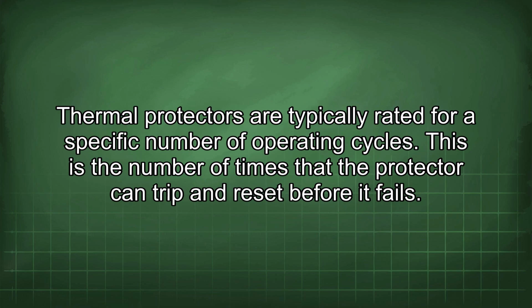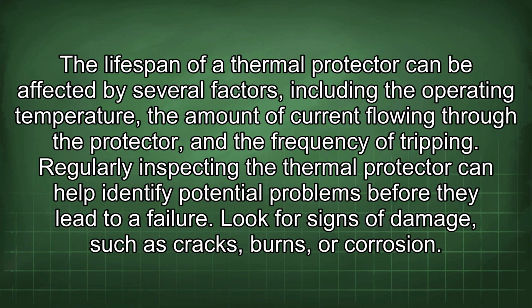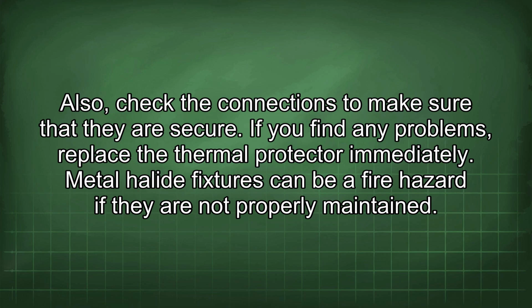Thermal protectors are typically rated for a specific number of operating cycles. This is the number of times that the protector can trip and reset before it fails. The lifespan of a thermal protector can be affected by several factors, including the operating temperature, the amount of current flowing through the protector, and the frequency of tripping. Regularly inspecting the thermal protector can help identify potential problems before they lead to a failure. Look for signs of damage, such as cracks, burns, or corrosion. Also, check the connections to make sure that they're secure. If you find any problems, replace the thermal protector immediately.